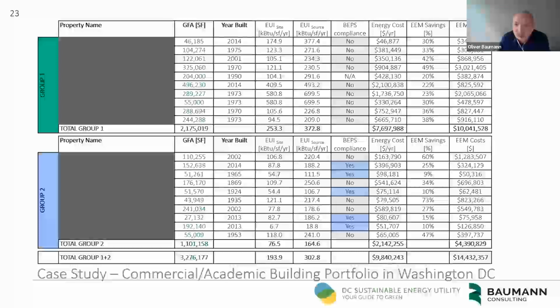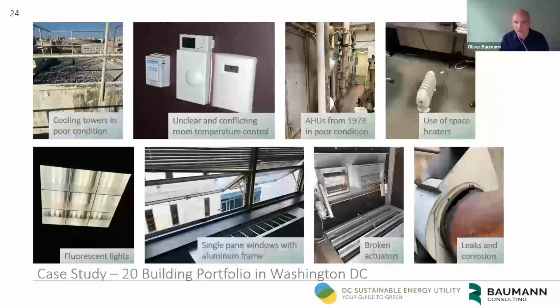We analyzed the site and the source energy use intensity because both metrics, you remember, have an importance. So we want to really understand both of them. We indicated whether those buildings are compliant with BEPS or not. Many of them are not compliant, so they need to do something. And then this is already a fast forward where we indicated the energy costs for that building. So we understand what every building is paying per year for energy, for utilities, and then also the potential energy efficiency measure savings. And you see that's all the way in the range of 30, 40. Some buildings have even 50 and 60% energy savings potential. So there's a lot of energy savings included here. And then also the cost of the energy efficiency measures. But we go a little bit deeper now into another table from the ASHRAE Standard that shows how we actually put those energy efficiency measures together.